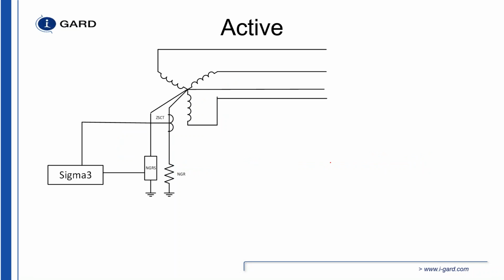When we actively determine the presence of the resistor or the integrity of the resistor, we have to monitor the line that's going from the NGRS or NGRX at this point to the XO bushing of the transformer or generator, and then back through the resistor. Sometimes we have two terminals here. One's called NN and one's called N. The reason we put that in there is to allow the user who's installing the gear to have two wires going to the XO bushing. We have to have two wires because that's the only way you can monitor the open circuit of this line right here. We put two terminals in there. If the customer wanted to jumper those, they can.